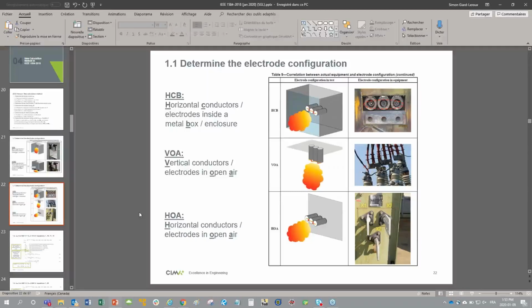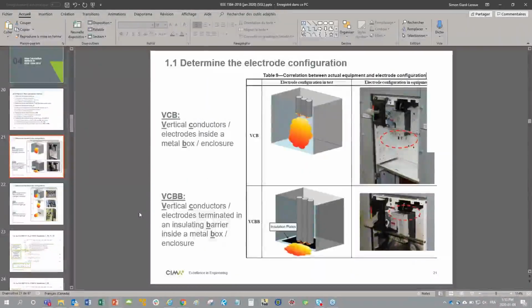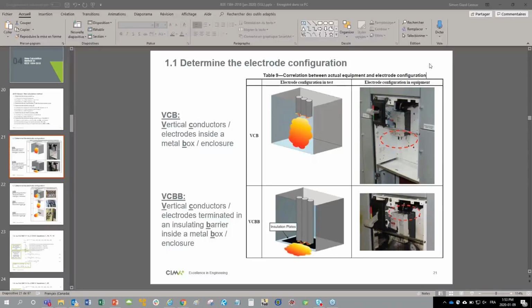All right. So this is interesting. The question is, for enclosure size, do you mean circuit breaker enclosure size, or what's the definition of enclosure? So the enclosure is the box, the cell that contains the breaker and the cables entering the breaker and the cables leaving. So, for example, in the figure you're seeing now, you have the cell. If it's an MCC, it's the MCC cubicle, the MCC cell, the MCC bucket. If you have a switchgear, it's the cell of the breaker container when you rack out your breaker. If you're working in a 480 volt panel, it's the panel size. So it's the area inside which the arc will propagate from.